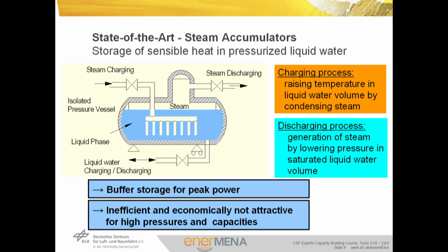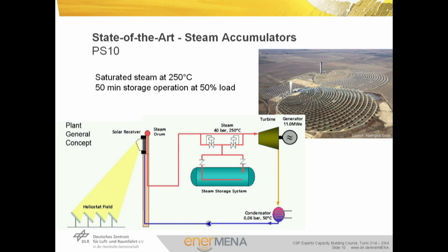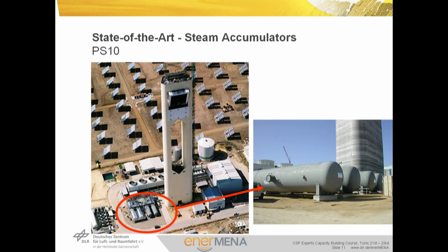The energy needed to generate saturated steam is taken from the sensible heat of the liquid volume. Pressure and temperature of the saturated steam provided during discharge is lowered. Steam accumulators are preferred as buffer storage for short-period power. Capacity-specific costs are dominated by the expense for pressure vessels and increase significantly at higher temperatures. An exemplary application is the PS10 and PS20 power plants, which use saturated steam from a central receiver, operating power blocks for about 50 minutes at 50% power. The main components are four pressure tanks filled with liquid water.